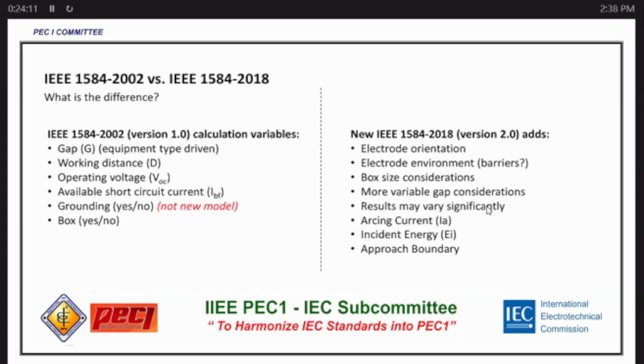So if there is grounding, that was not yet modeled previously. If there is a box, you could choose with that, so there is a table for that, if you have your IEEE 1584. But when it comes to the new standard or new version of IEEE, there is what we call electrode orientation.